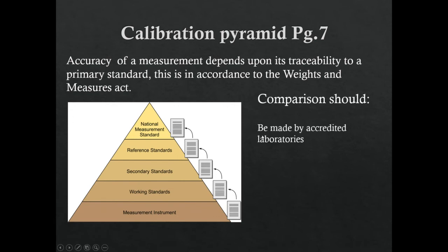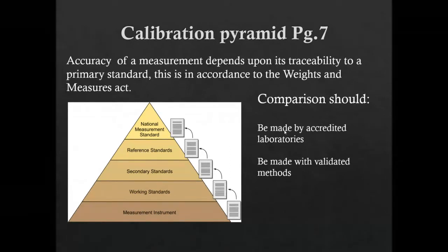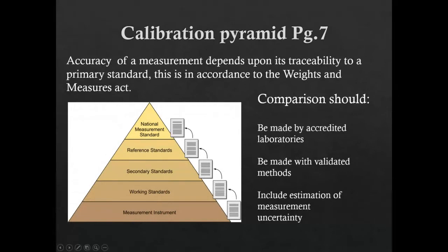Importantly, comparisons should be made by accredited laboratories — Measurement Canada will tell you who is and isn't accredited. Comparisons must be made with validated methods — proper procedures — and must include an estimation of measurement uncertainty, that plus-or-minus value we hold it to.